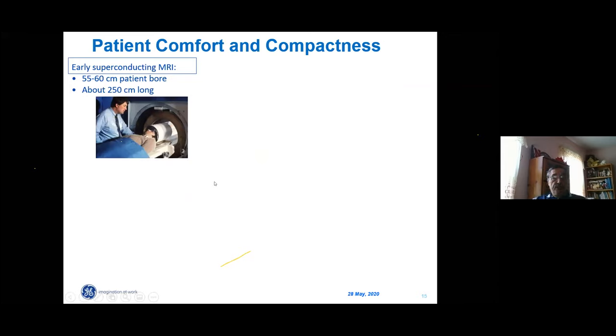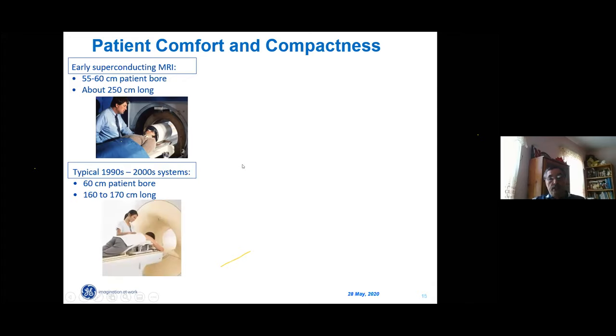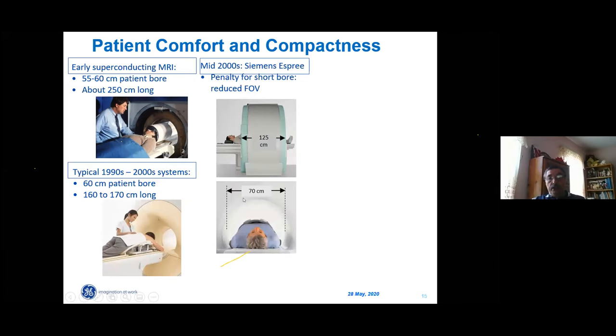Patient comfort and compactness. Just a brief history. In early MRI, when customers wanted MRI at any cost, the first scanners had a patient bore of only 55 centimeters and long, over 2.5 meters long magnets. Then in the 1990s, the industry introduced 60 centimeter standard patient bore and 160 to 170 centimeters long magnet with by far better patient comfort. In mid 2000s, Siemens started a revolution. Significantly shorter magnet, often at the expense of smaller field of view. Field of view was reduced, but Siemens introduced electronic technology to make a better image quality, even with smaller field of view. And since then, this 70 centimeter patient bore became standard.